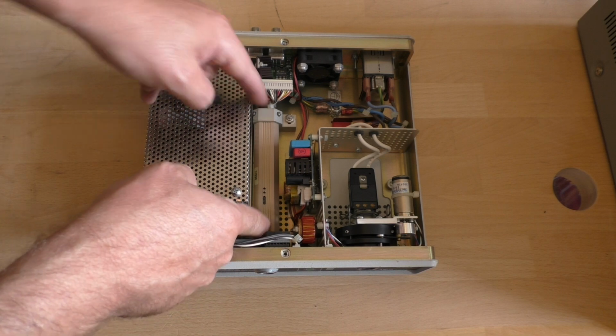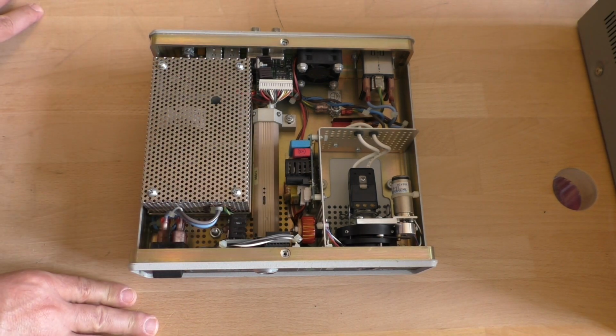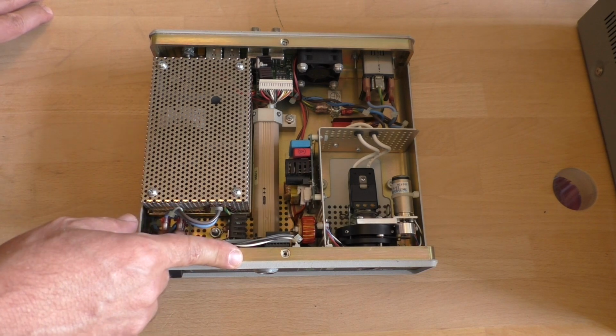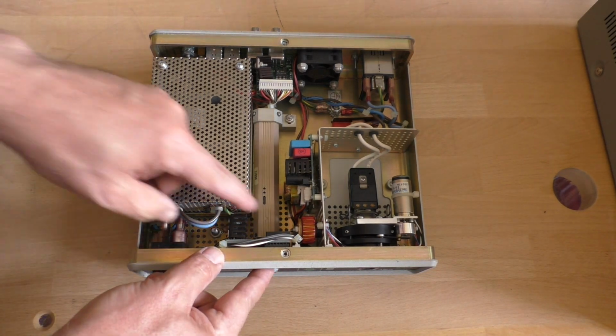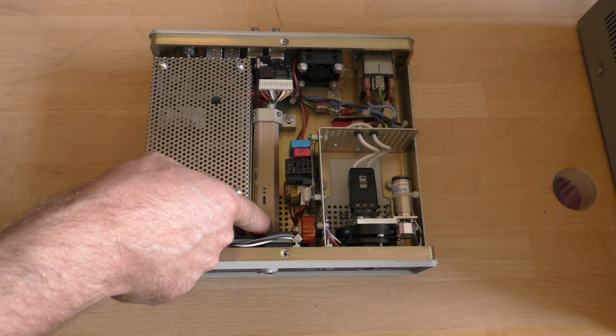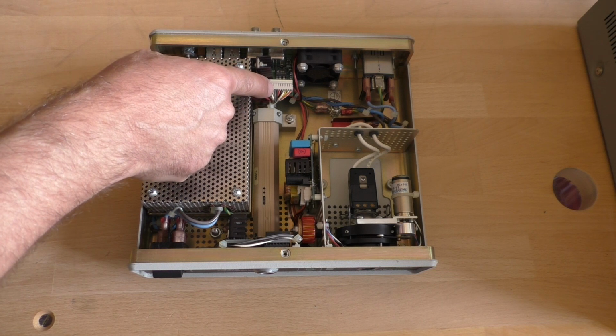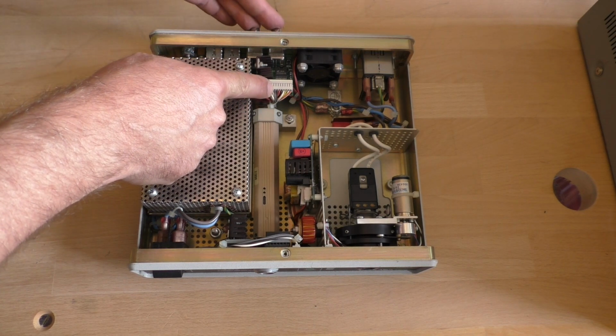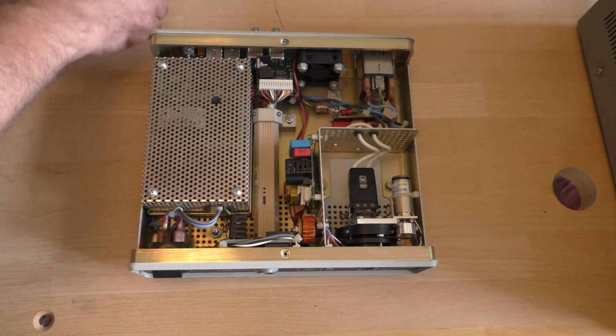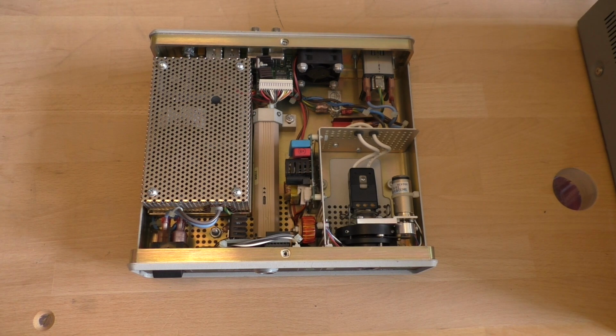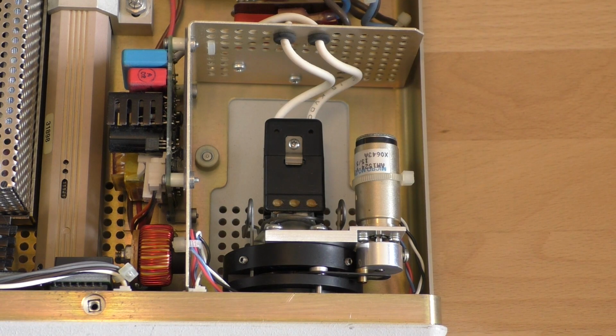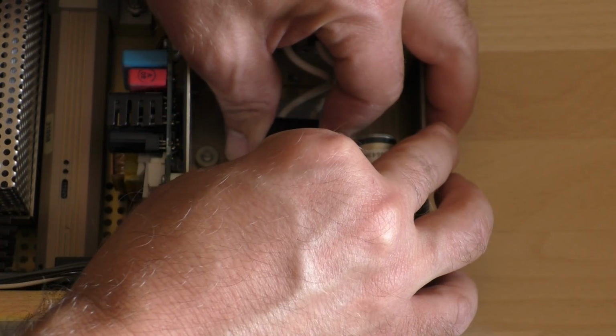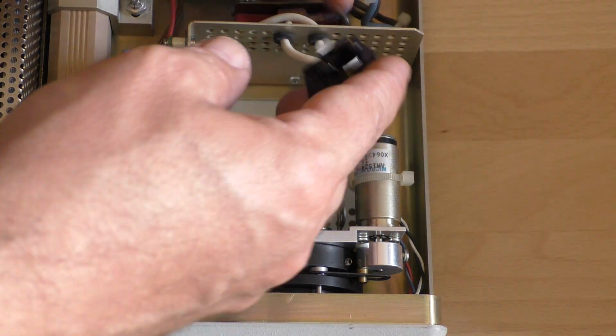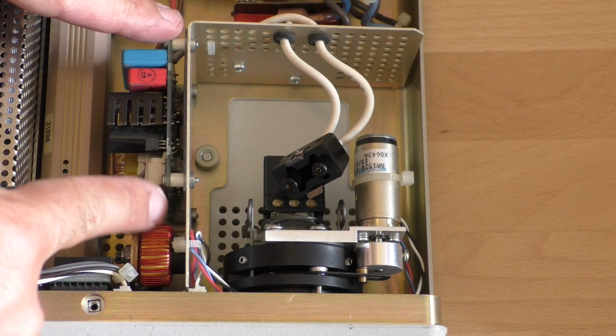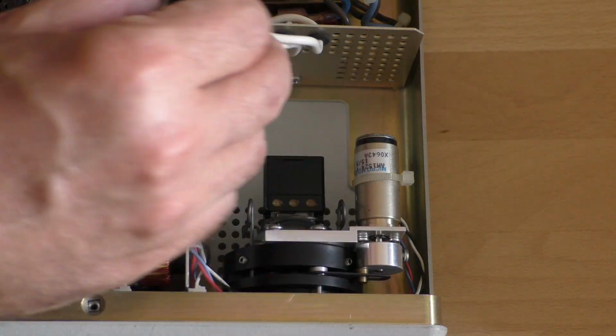And we have this long module here that looks a little bit special. I know that's the camera module, because here is the camera connector that goes more or less directly into this device. And here on the back side are the two BNC connector outputs for the video signal. And I just spilled all the screws all over the floor. Replacing the bulb is pretty easy. You just disconnect the connector here. You can see cables go directly to the lamp power supply module.